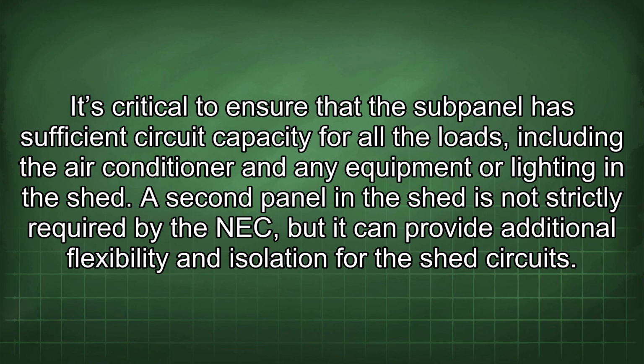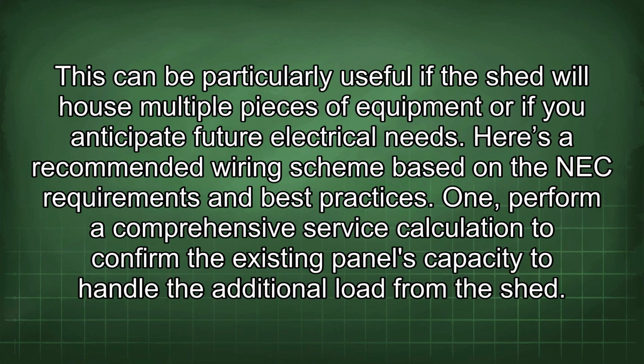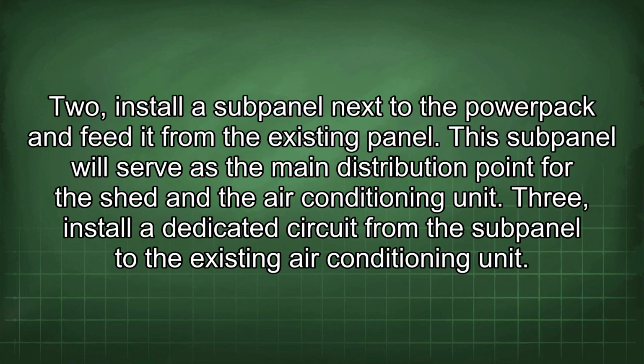A second panel in the shed is not strictly required by the NEC, but it can provide additional flexibility and isolation for the shed circuits. This can be particularly useful if the shed will house multiple pieces of equipment or if you anticipate future electrical needs. Here's a recommended wiring scheme based on the NEC requirements and best practices. 1. Perform a comprehensive service calculation to confirm the existing panel's capacity to handle the additional load from the shed. 2. Install a subpanel next to the power pack and feed it from the existing panel. This subpanel will serve as the main distribution point for the shed and the air conditioning unit.